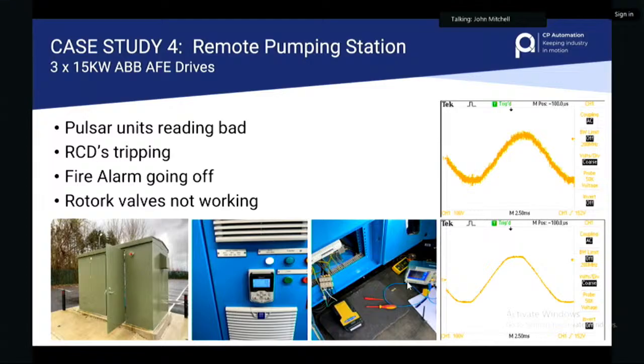We've just had this case here—actually a second case of this in Denmark today. One of our partners in Denmark just called to say they've got a problem with a product called a Rotork valve, an automated valve that rotates for borehole pumps. Whenever the ABB drives were running, the valve and well depth sensors were going crazy—they just couldn't read or operate. We installed one Sine Tamer and all the problems went away, all of them. This problem had been investigated for nine months.